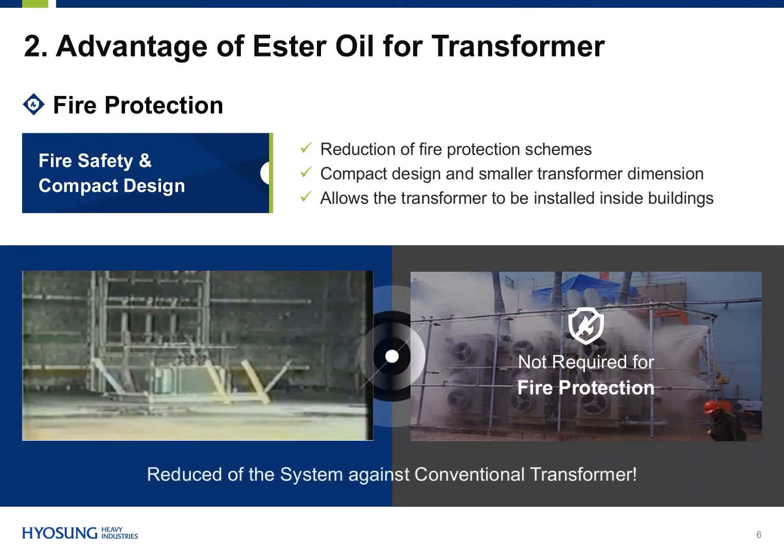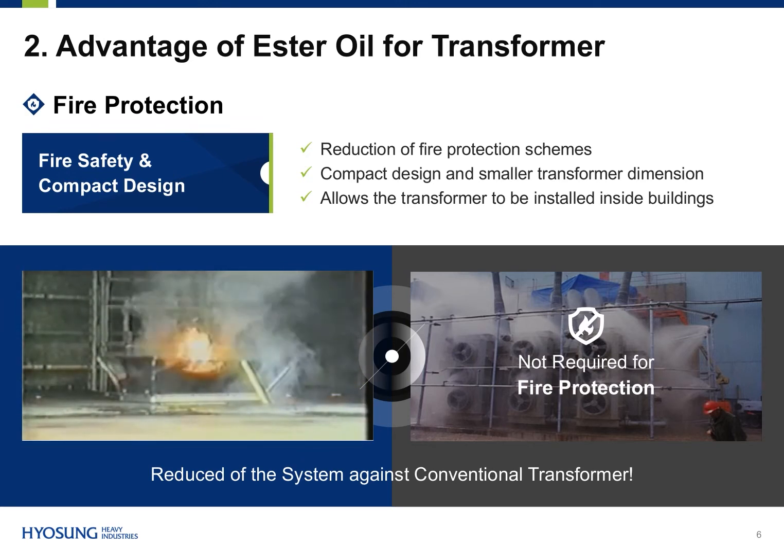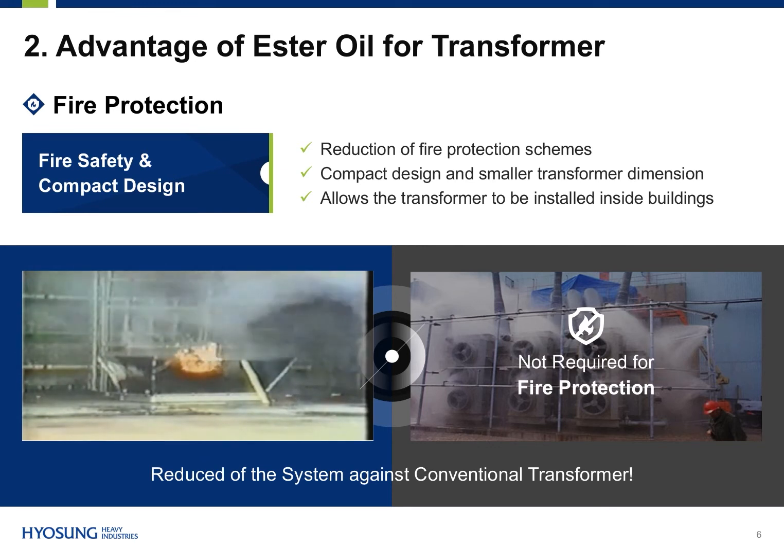We will now see a video of an explosion test for a synthetic Ester Oil. You can see that the fire is self-extinguished. Developments in Ester Oil transformers provide clean fire protection advantages.